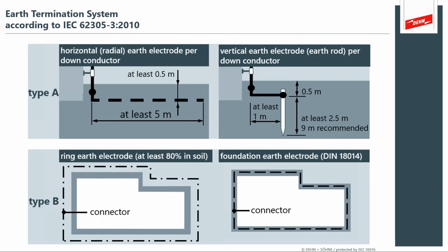So I'd like to show our earth termination slide. We talk a lot about earthing as part of a lightning protection system. Earthing is also important, of course, for electrical power safety as well. But this slide gives us a really good look at the type A and the type B earthing electrode system. The type A consists of horizontal radial earth electrodes that we see very commonly when you have very rocky soil where you have to bury the electrode, but this is in contrast to what you see very commonly, certainly at your residential main service entrance. You'll have a vertical earth electrode, a ground rod. And of course, there's a lot in the electric codes that give you advice about how deep the rod should go and what the actual earthing impedance is that you're looking for. Residential, 25 ohms. A lot of industrial applications want up to 1 ohm maximum earth electrode impedance.